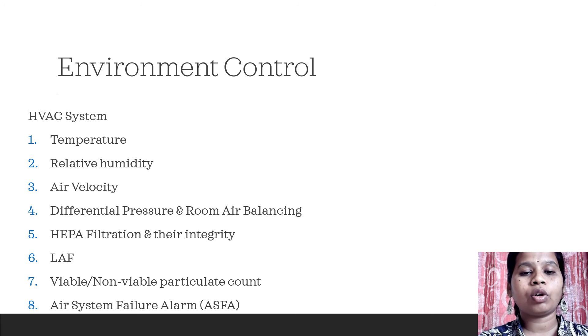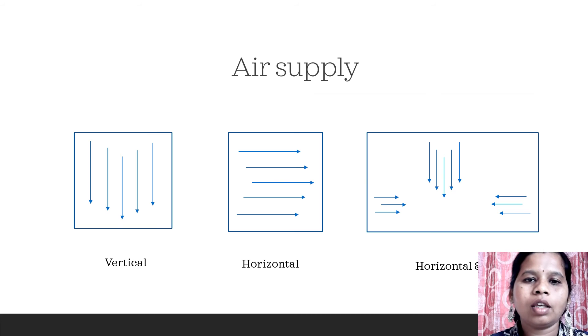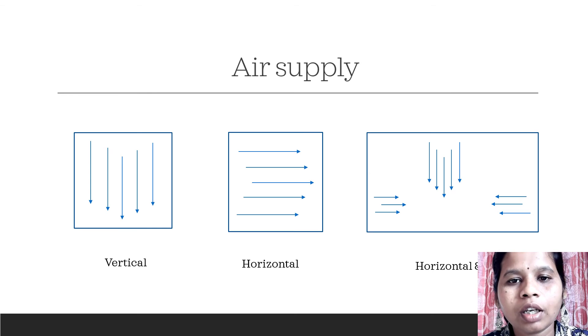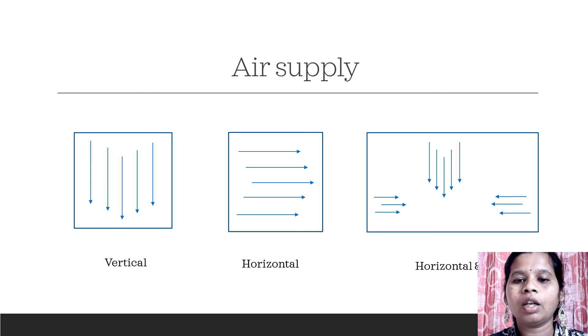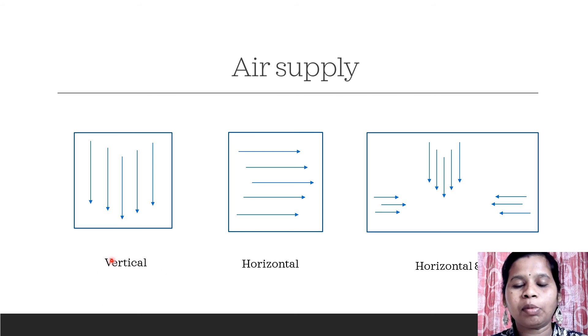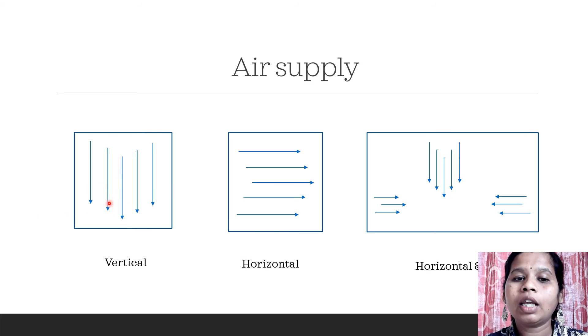For environmental control in different grades, laminar air flow units are used. These units have different types of air supplies — the air flow can be vertical, horizontal, or a mixture of both. The vertical type is the most preferred, where in the closed cabinet of the laminar air flow unit, air comes from the top, flows downward through the working area, and flushes away all particulate matter.